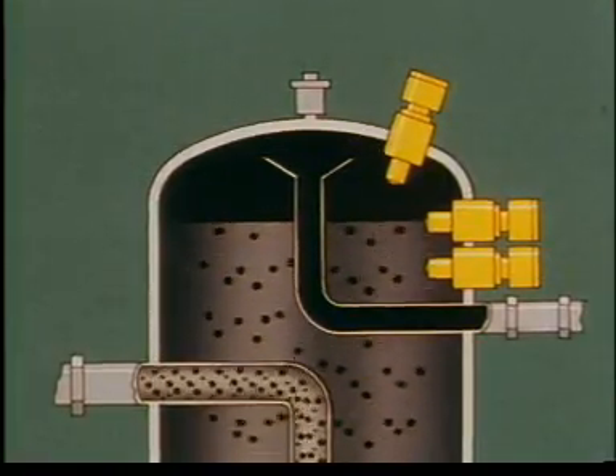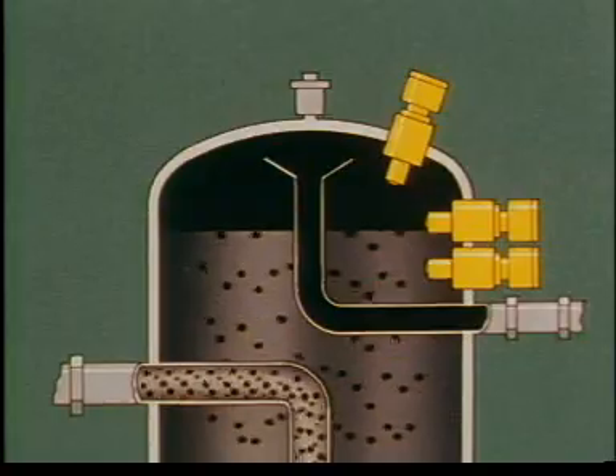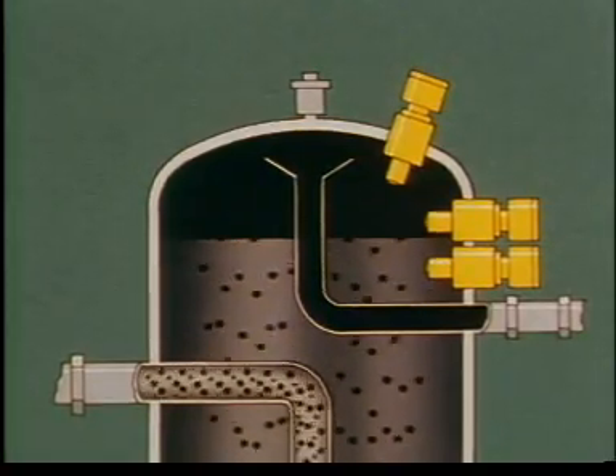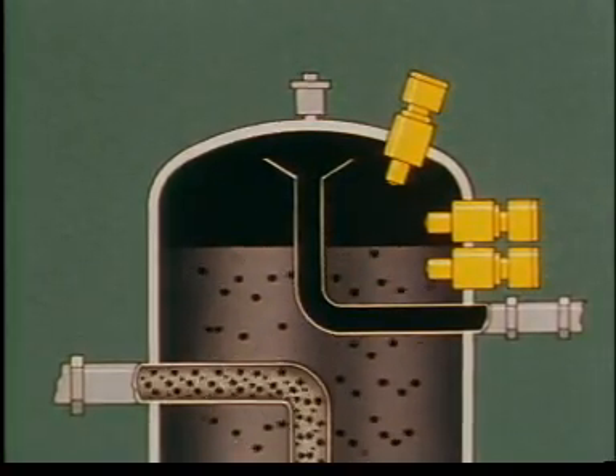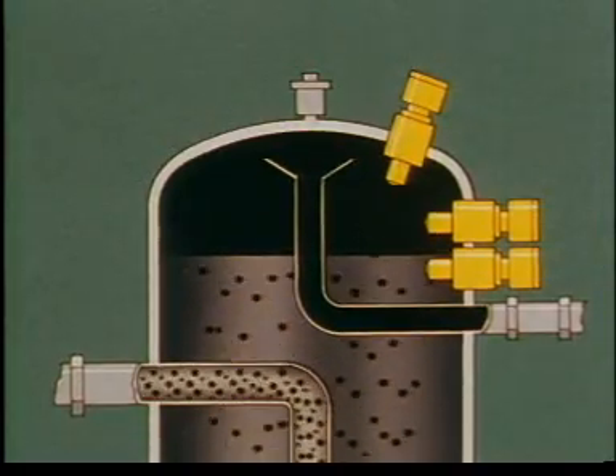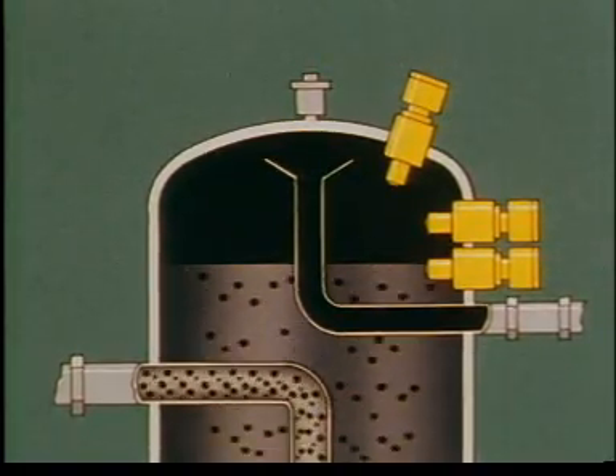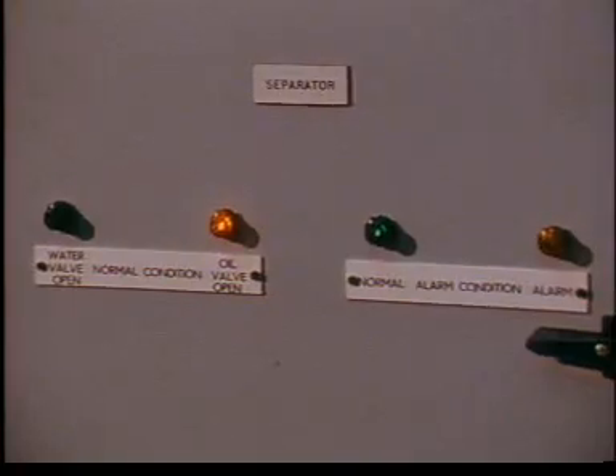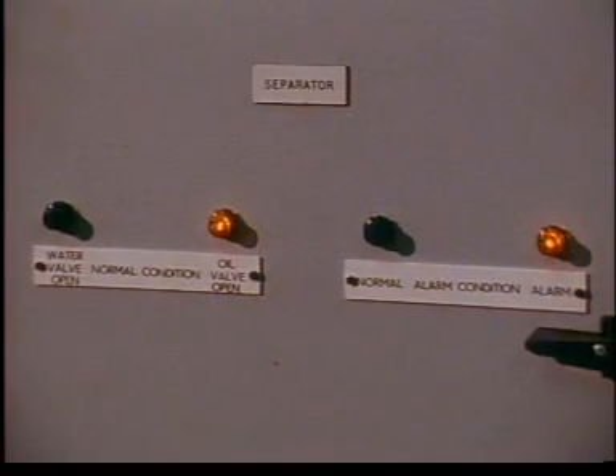The third and lowest probe is a safety device. If a fault develops in the middle probe so that the oil outlet valve is not opened when this probe is immersed in oil, the oil-water interface will continue to descend until the third probe is immersed in oil. This will illuminate the low-level oil light on the control panel and can be arranged to trip the pump motor or sound an audible alarm.